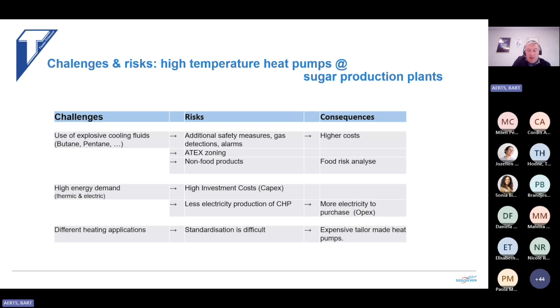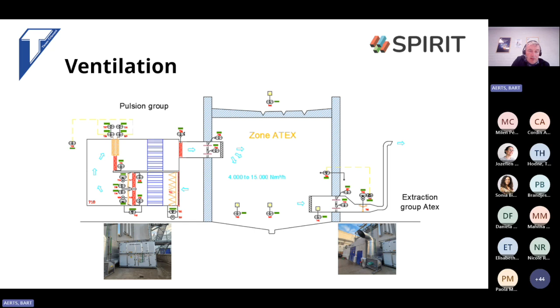An additional point we had to build was full ventilation: one for cooling the area, and one in case of leaks. So we have a pulsion group and an extraction group which is always on, even if the heat pump is out of service or in maintenance. As pentane is heavier than air, we have detectors at the bottom, and in case of a leak we increase the extraction amount to take it out of the area, staying always at a safe LEL level so we don't approach an explosive environment. This is also a full installation which is needed in our setup.